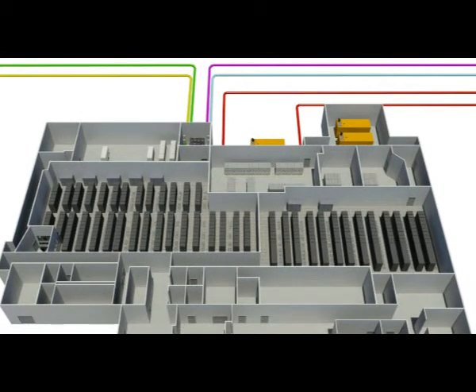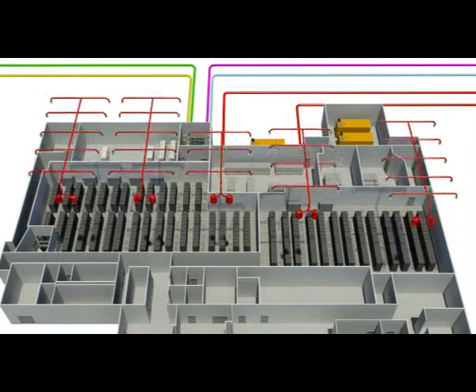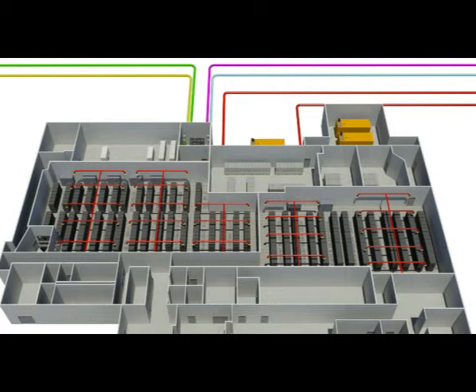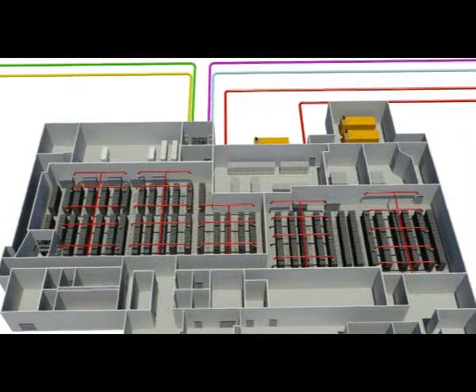The facility is protected from fire by a state-of-the-art Very Early Smoke Detection Apparatus, or VESDA, fire suppression and thermal detector system, while a dry pipe pre-action sprinkler system completes the picture of a worry-free data center environment. The new data center has FE25 gas throughout the entire facility.